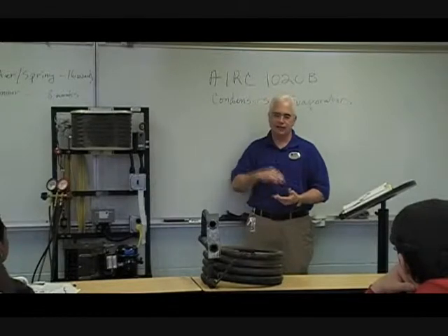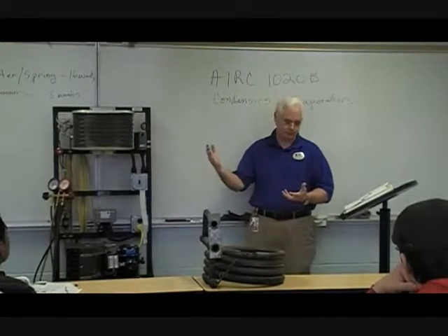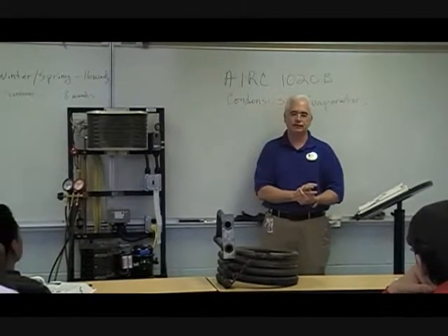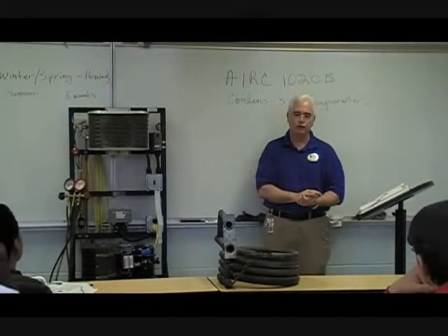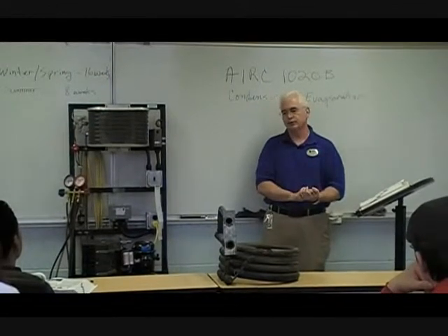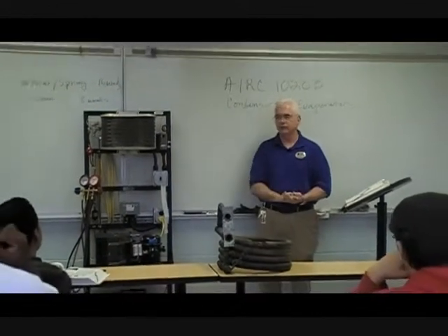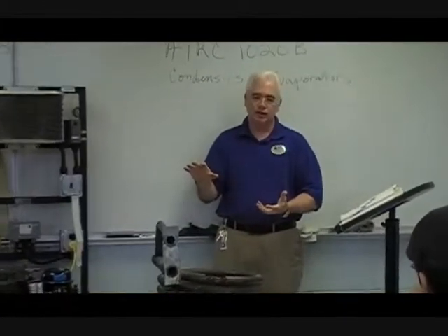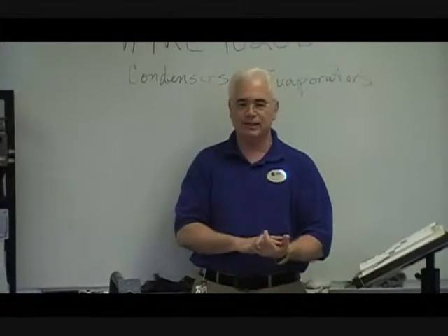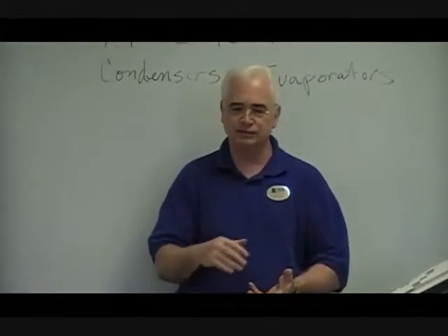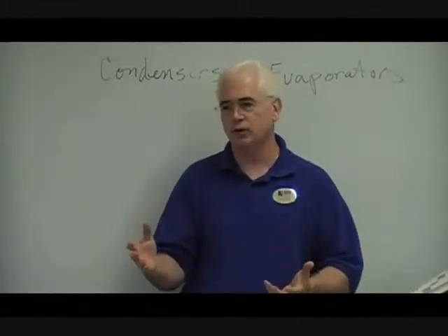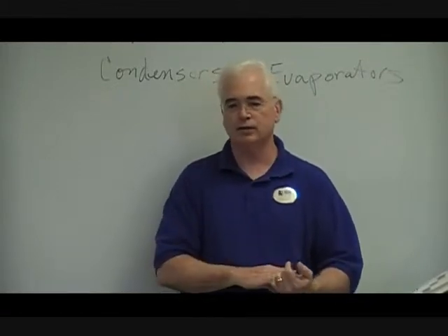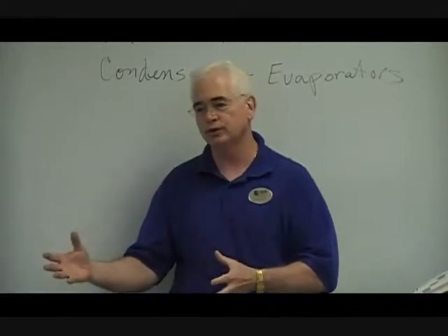And that's how the heat is rejected. Now, you've got to have a medium of exchange, whether it be air or water, that is of a cooler temperature than the hot refrigerant gas. If the hot refrigerant gas or vapor is about the same temperature as your medium of exchange, no temperature transfer is going to occur. And it all goes back to the basic fundamentals of HVACR. Heat always travels toward a cooler temperature.